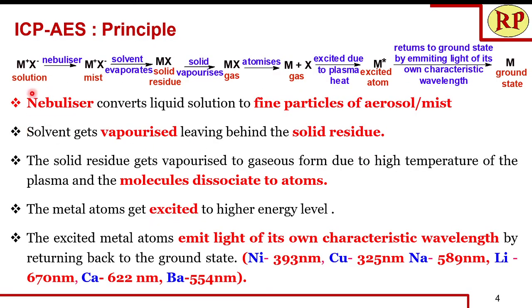When the solution enters the nebulizer along with the argon gas, it gets converted to an aerosol mist. When this is sprayed into the plasma at a temperature of almost 10,000 Kelvin, the solvent evaporates leaving behind the solid residue, which further vaporizes to form the gaseous compound. This atomizes, and the metal atom gets excited by the plasma heat. The excited atom returns back to the ground state emitting light of its own characteristic wavelength — for example, nickel at 393 nm and copper at 325 nm. All elements present will get excited and emit at their own characteristic wavelength.